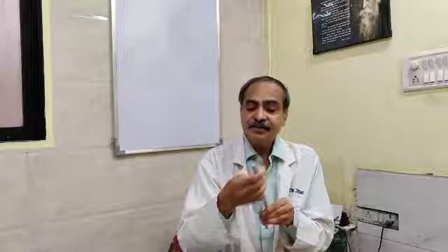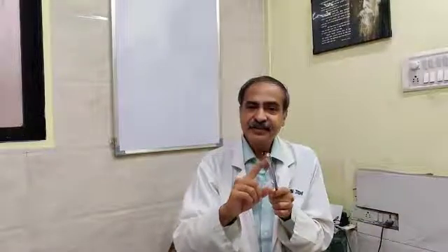The vesical end is made up of Teflon coated with ceramic, but this has to be checked properly, because as long as the Teflon and ceramic coating is adequate, the sheath doesn't form a part of the circuit. So high frequency current, and hence high temperature, is not transmitted to the metal part of the sheath and hence to the urethra.